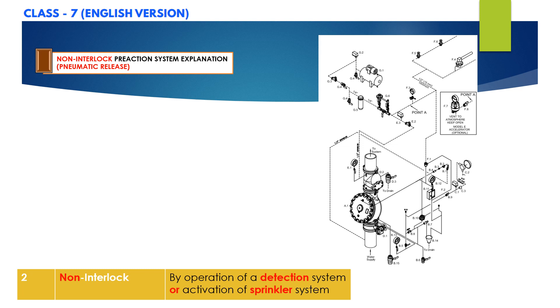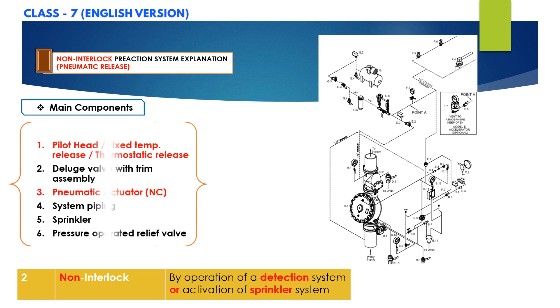Now let us go through the pneumatic release type non-interlock pre-action system. The concept is the same with only slight modification in components. As you can see on screen, there is no electric release panel or electronic devices. In this pneumatic release type, you will have pilot heads, fixed temperature release sprinklers, or thermostatic release devices, along with the deluge valve with complete trim assembly and a pneumatic actuator — there is no solenoid valve. System piping connected to the sprinklers and a pressure-operated relief valve are also present.